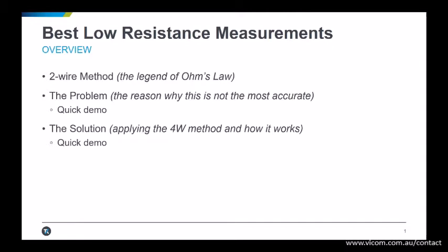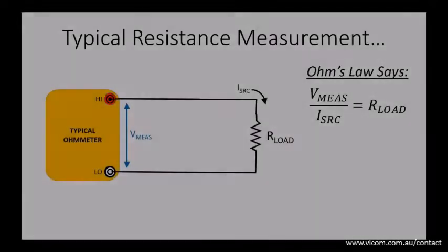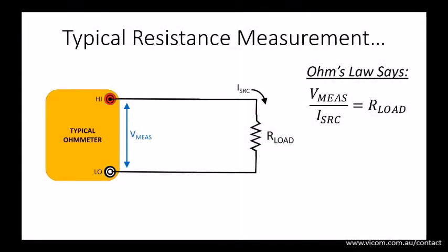The resistance function of your typical ohmmeter or multimeter will source a known current to your device under test, the resistor, and perform a voltage measurement at the terminals where the test leads are inserted. The resistance value is calculated using the source current and measured voltage values.